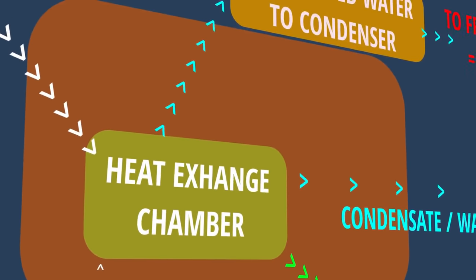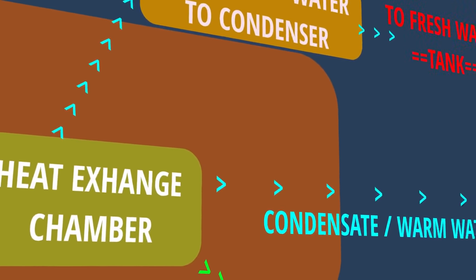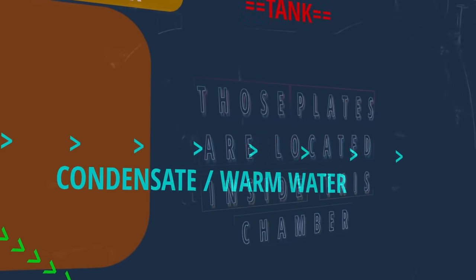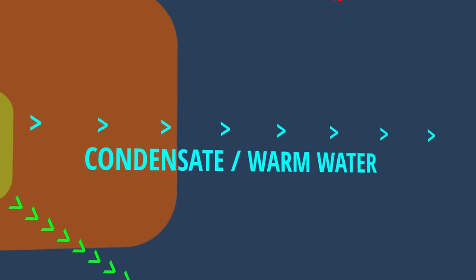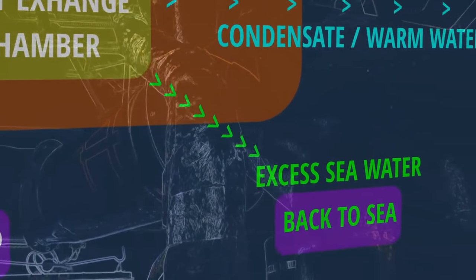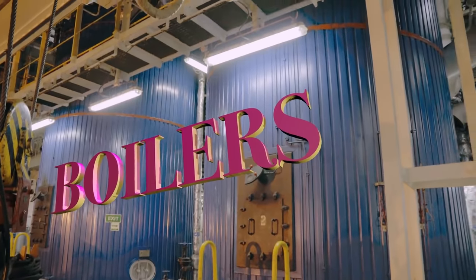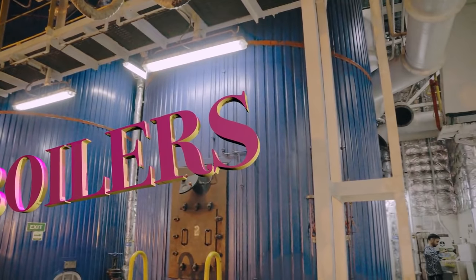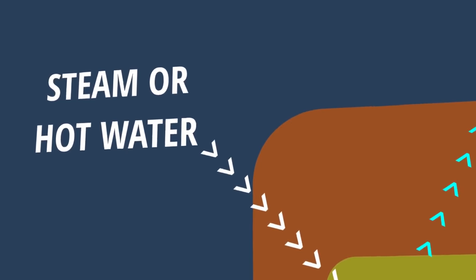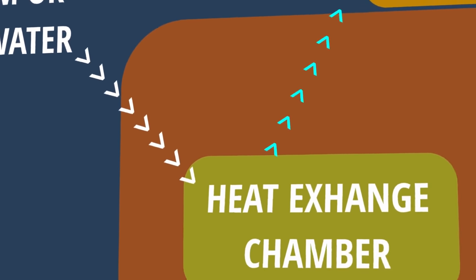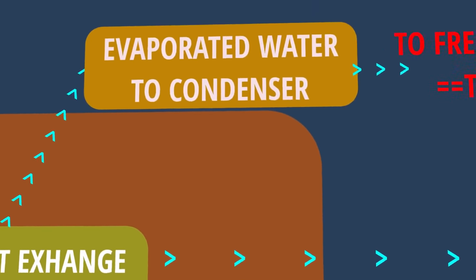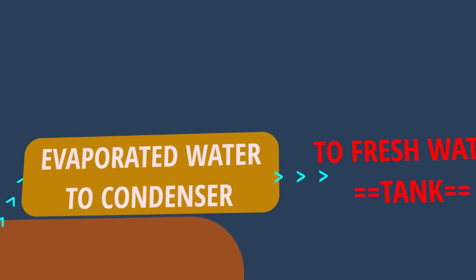Our pump will suck the sea water around the vessel and put it into the fresh water generator. In the fresh water generator, we have two things. One thing is that we put hot water in the fresh water generator and the water will evaporate from the plates. We can also use steam to generate fresh water. When the plates inside the heat exchange chamber are heated, your sea water will evaporate and solid deposits — the impurities — will stay there.